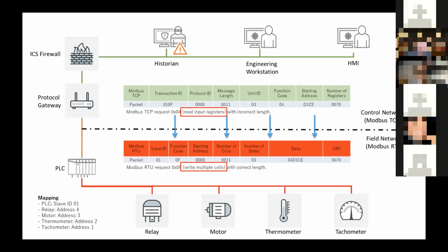When it goes through the protocol gateway, it comes out looking exactly the same, but in Modbus RTU, that actually looks like a write multiple coil packet with the correct length, with all of the valid data in there.